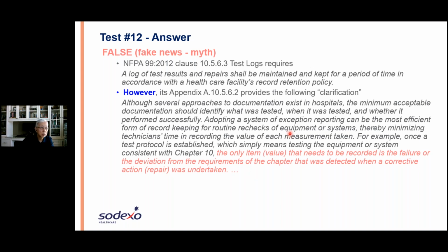It's stated here, exception reporting. In other words, if it's falling within the specified range, you can simply say PM passed or pass the CM testing at the end of your repair, and therefore nothing needs to be done. Okay, you don't need to write down those numbers. And by the way, this is not only saving time, but also saving you most likely a lot of headaches down the road because someone can fat finger in a wrong digit.